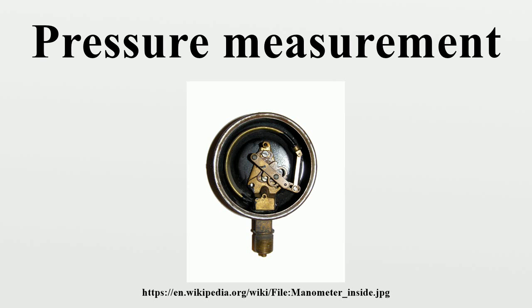A vacuum gauge is used to measure the pressure in a vacuum, which is further divided into two subcategories: high and low vacuum. The applicable pressure ranges of many of the techniques used to measure vacuums have an overlap. Hence, by combining several different types of gauge, it is possible to measure system pressure continuously from 10 millibars down to 10^-11 millibars. Absolute, gauge, and differential pressures: zero reference.